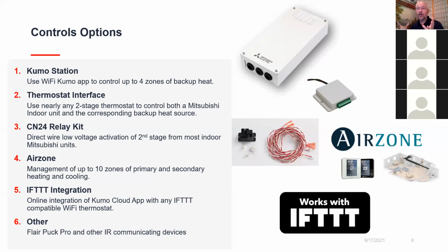Okay, so number two, thermostat interface. Mitsubishi, and other manufacturers too, have thermostat interfaces. Our thermostat interface plugs into our communication port, the CN105, and then there's a series of dip switches on the inside of that you can adjust. It has standard thermostat connectors, W's and Y's and R's. You would run your standard thermostat wire to whatever your favorite flavor of dual stage thermostat is, and use presumably the existing thermostat connections going down to whatever zone. That could be for a central system for the entire house, or for multiple thermostats throughout the house. A lot of different options there.